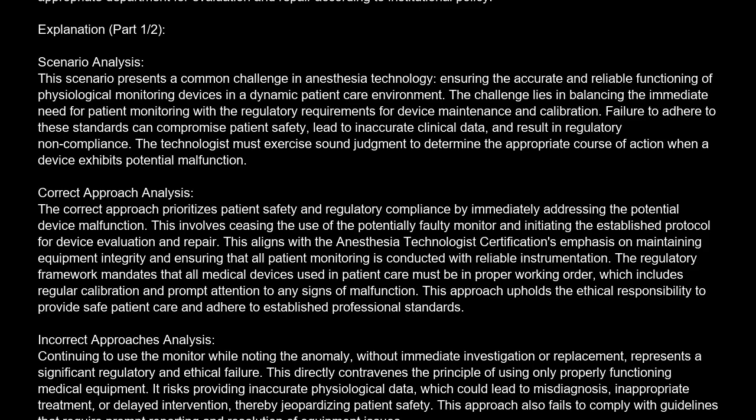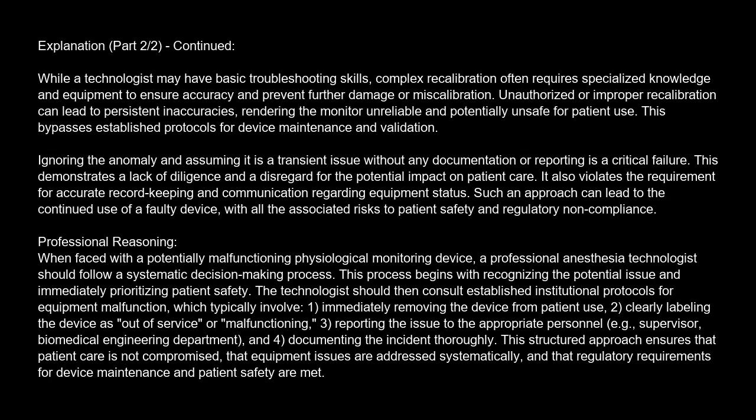Attempting to recalibrate the monitor in situ without following the manufacturer's specific guidelines or without proper authorization from a qualified biomedical engineer is also a regulatory and ethical failure. While a technologist may have basic troubleshooting skills, complex recalibration often requires specialized knowledge and equipment to ensure accuracy and prevent further damage or miscalibration. Unauthorized or improper recalibration can lead to persistent inaccuracies, rendering the monitor unreliable and potentially unsafe for patient use. This bypasses established protocols for device maintenance and validation.